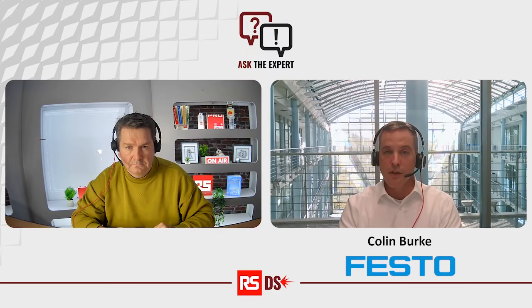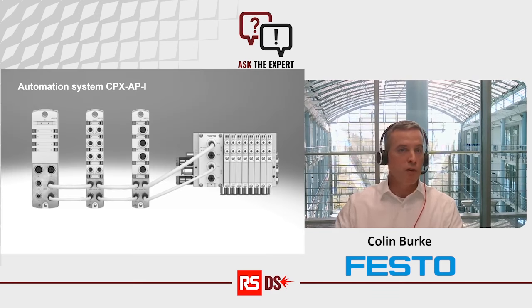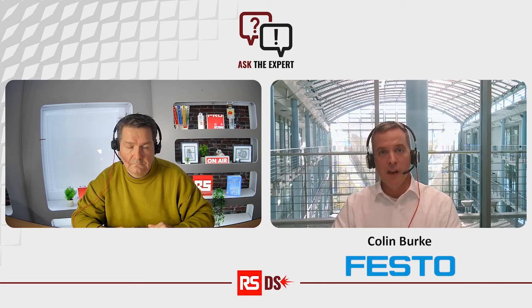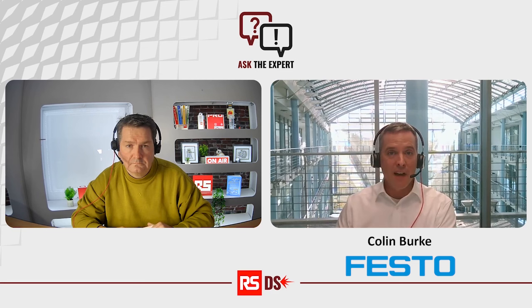So we've got 3 options. Also going back to this mix and match open philosophy, you have the decentralized CPX AP-I, put them around the machine as you need. You can have up to 50 meters of cable between them. And from one bus node, so one entry point to your PLC, you can have a further 79 modules daisy chained throughout your machine. And then you can also go on to the CPX AP-A, which is just a modular block with all the remote IOs together, either standalone or also on the valve terminal. And you can mix and match. You can go into one, out from the other.